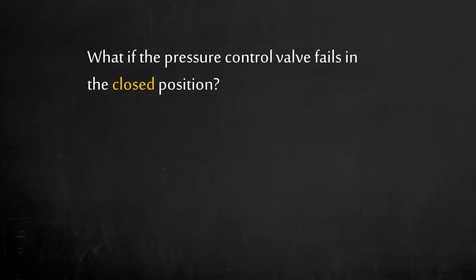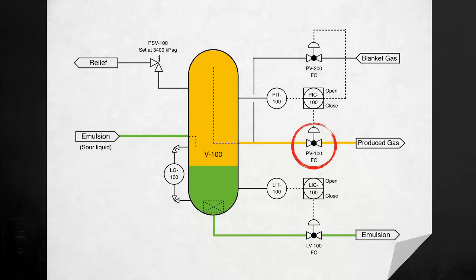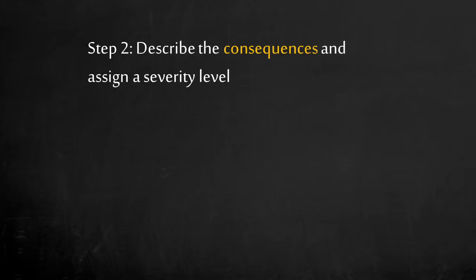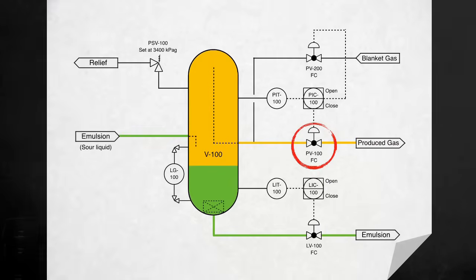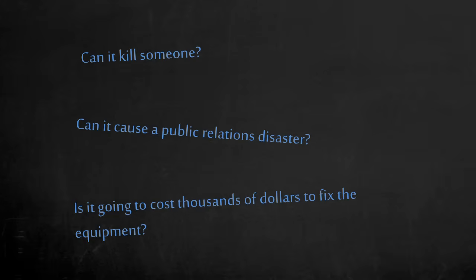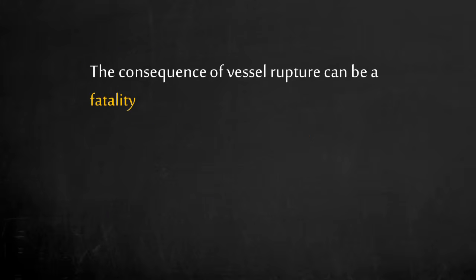What if the pressure control valve fails in the closed position? What if vessel V100 were to overpressure leading to rupture due to inadvertent closure of the pressure control valve? Can it kill someone? Can it cause a public relations disaster? Is it going to cost thousands of dollars to fix the equipment? These may be some of the consequences that matter to you and your company, and the risk should be managed. Based on some discussion, the team has agreed a vessel rupture can lead to a fatality. Now one of the two elements of risk is established. What is the other element?